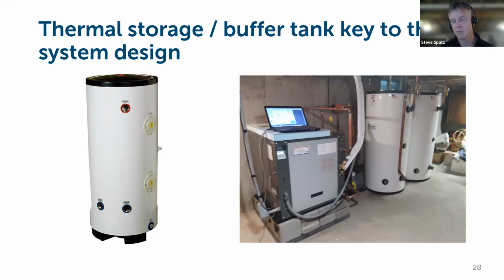And any of the heat pumps that we're talking about here have capacity that will go down to -20 and below. That output capacity does drop as outdoor temperature drops, just like with any heat pump. There's less BTUs to pull from the ambient air as it gets colder outside. But with the right design and the right capacity factored in, there's enough time and enough storage to be able to maintain enough temperature in that tank to meet whatever the distribution side of the equation is going to see during cold outdoor periods.